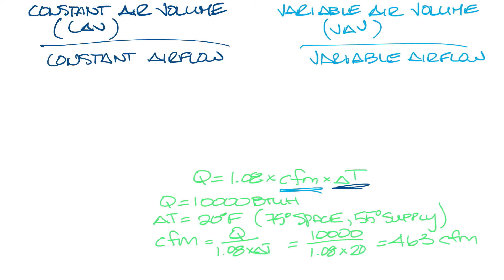So this holds true for our constant volume and variable air volume system, but what happens if we increase the load to 12,000 BTU? So now on our variable air volume system, we need to go calculate CFM again. So CFM equals 12,000 divided by 1.08 times 20, and that equals 556 CFM. So we need 556 CFM in this system to handle the 12,000 BTU load.